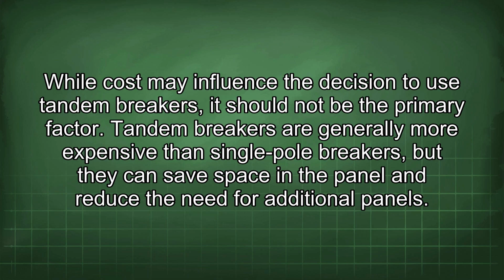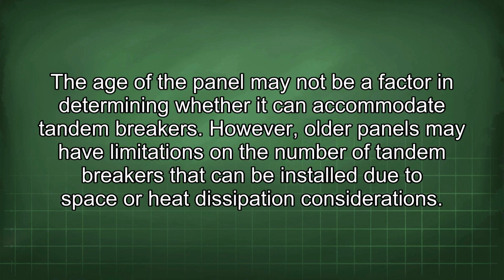While cost may influence the decision to use tandem breakers, it should not be the primary factor. Tandem breakers are generally more expensive than single-pole breakers, but they can save space in the panel and reduce the need for additional panels. The age of the panel may not be a factor in determining whether it can accommodate tandem breakers. However, older panels may have limitations on the number of tandem breakers that can be installed due to space or heat dissipation considerations.